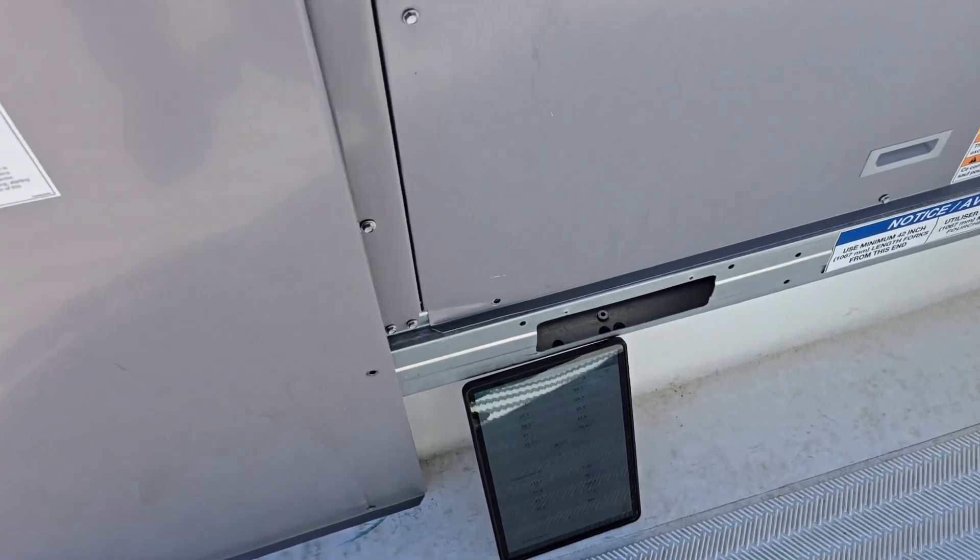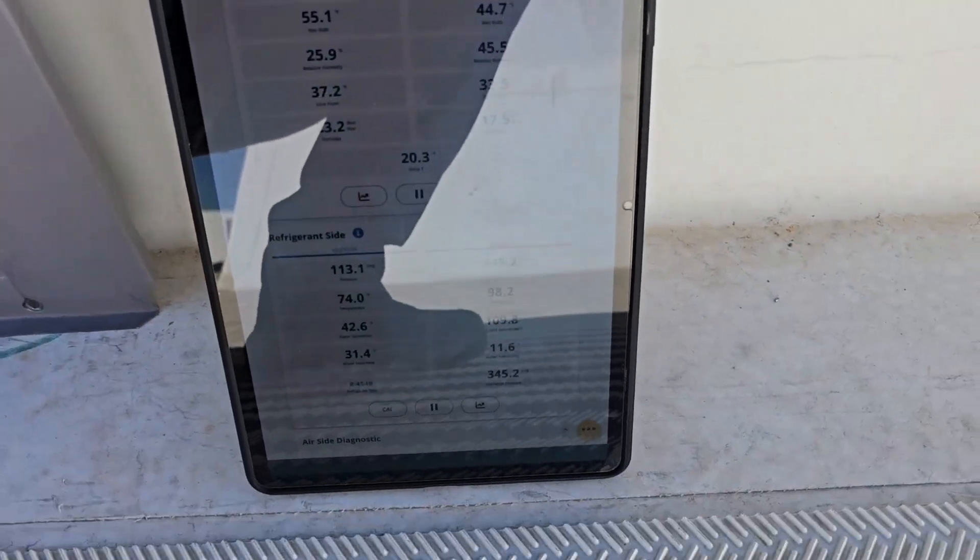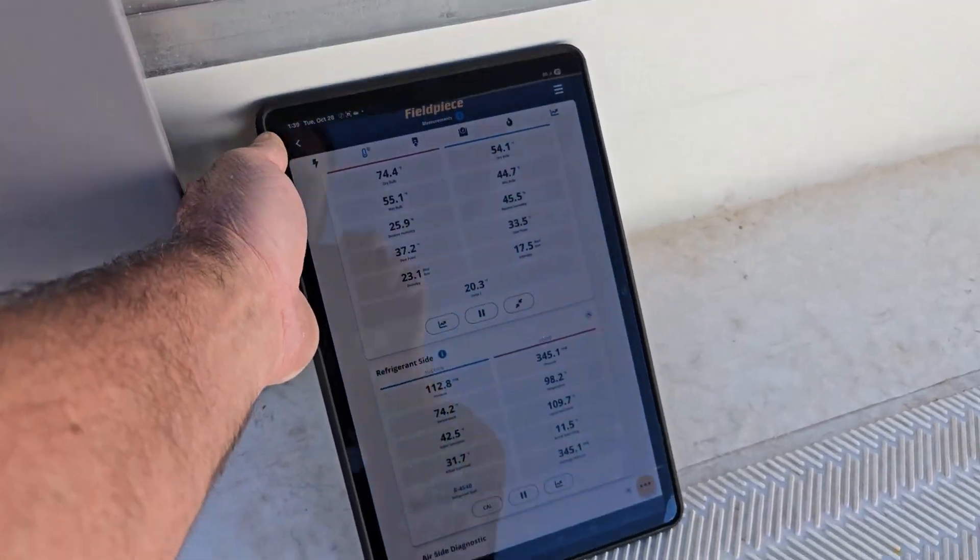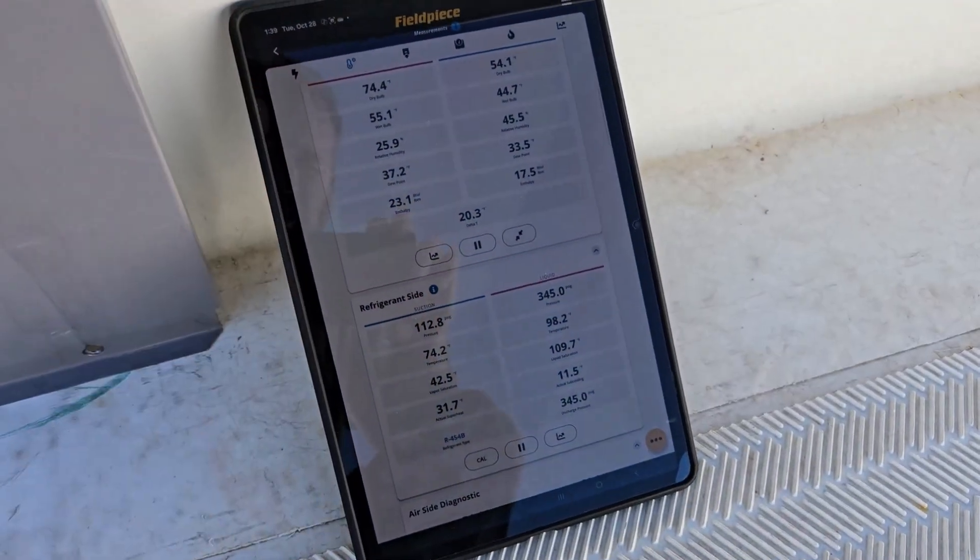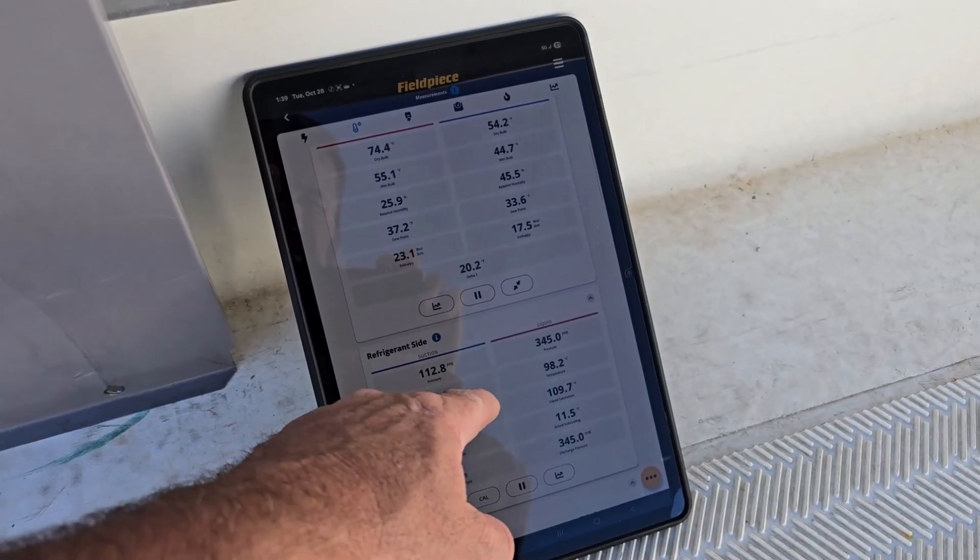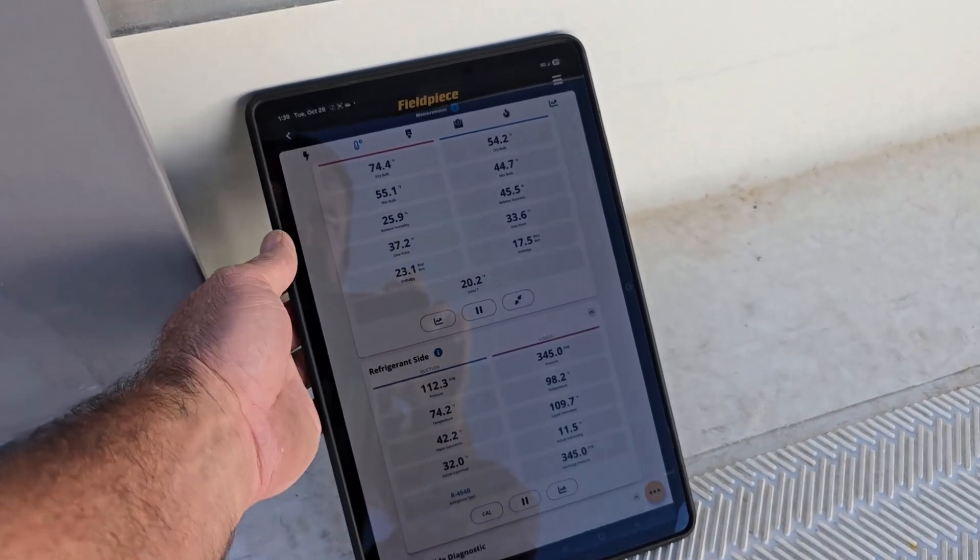So earlier all those sensing bulbs was off for a while and I put it back on. The second stage is working great. This second is going to start pumping down kind of a little bit. TXV wasn't opening back up. Now I just dropped it to first stage again and everything looks great. Good pressures, a little over 20 degree split temp.